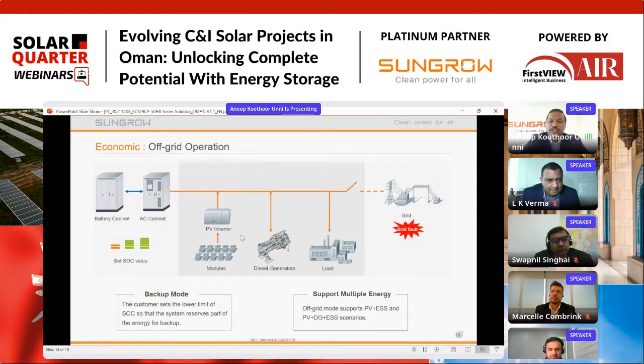Here we need to check the DG capacity, and arrive at the correct PV sizing, and also determine the best capacity for the PCS. When talking about the best capacity of the PCS, as discussed earlier, the maximum size in off-grid application is 6 units in parallel.